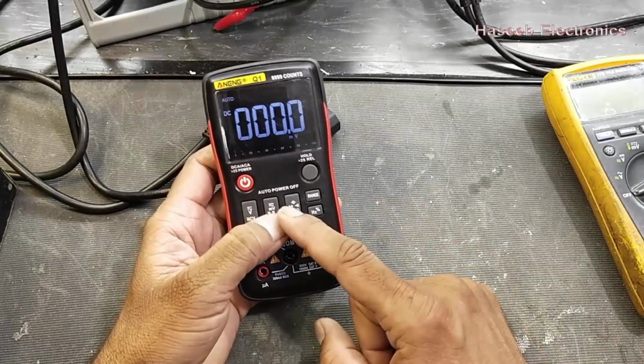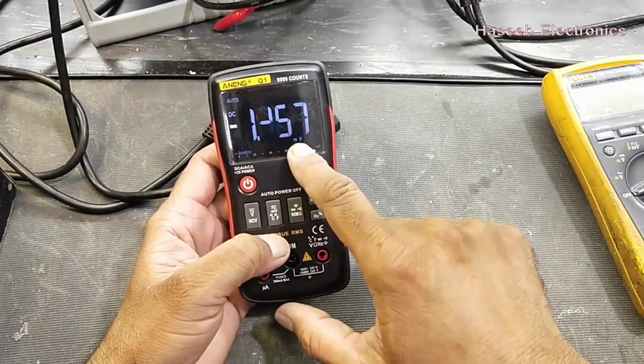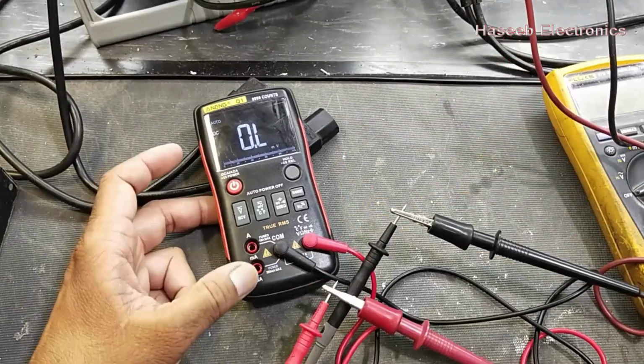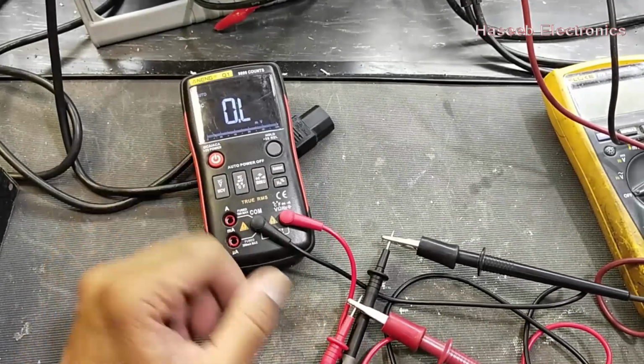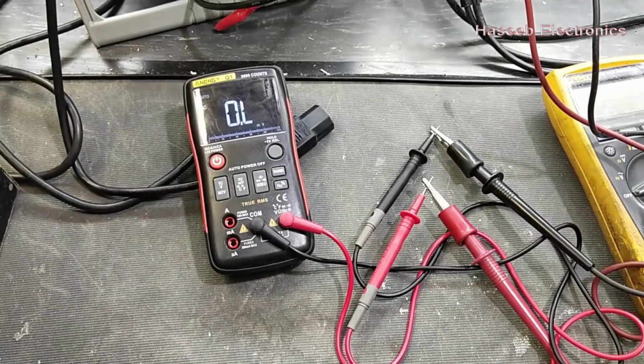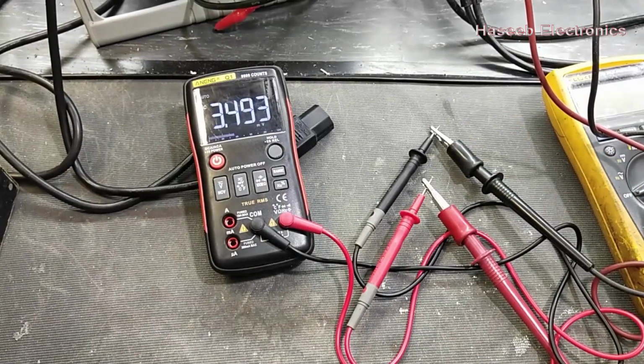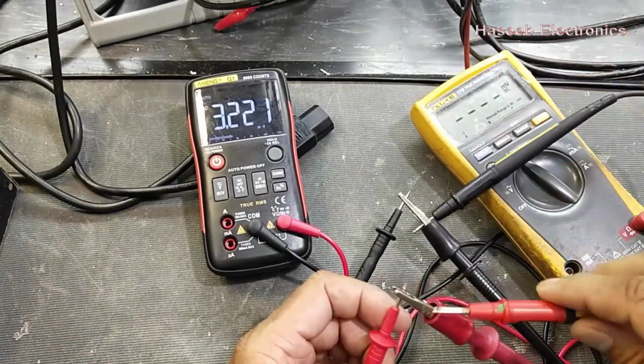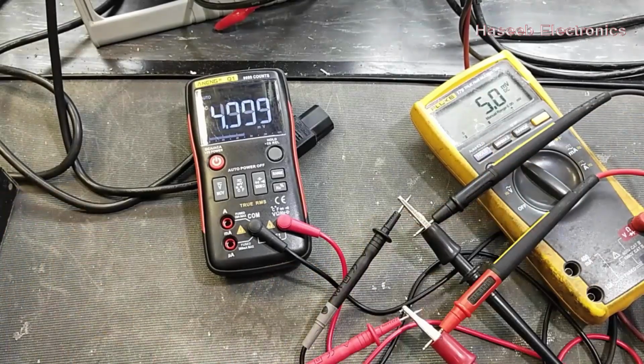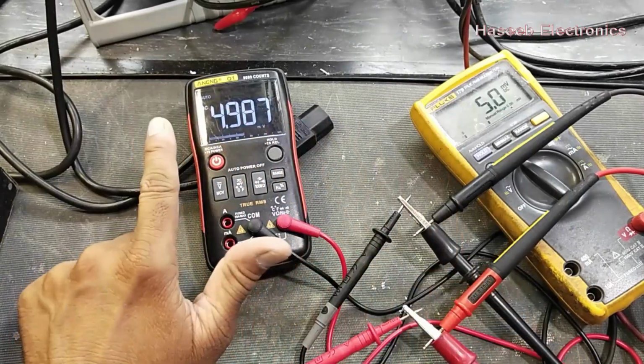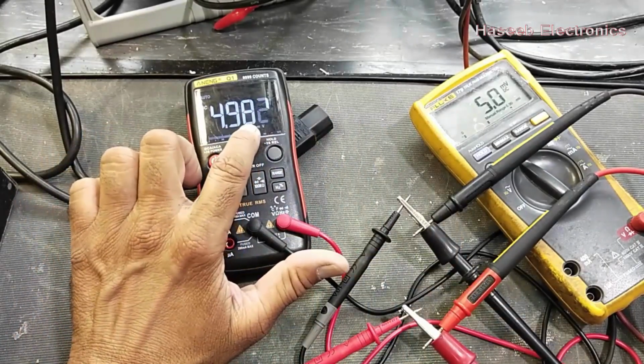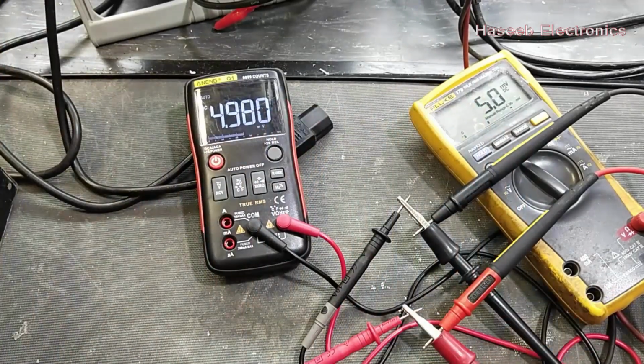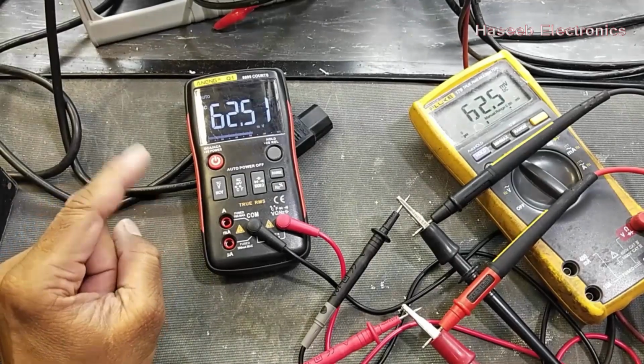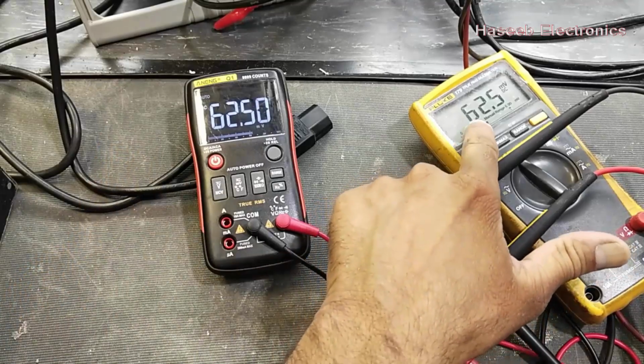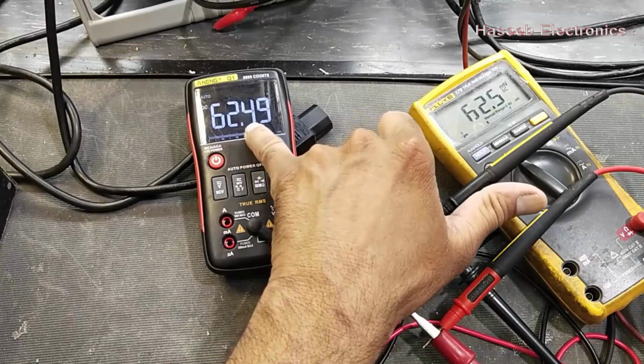To test millivolt in DC, power on, press this button, and now we are in millivolt range in DC. If I apply more voltage, it says over range, OL, overload, meaning the input applied is more than the multimeter range. When I decrease, I applied 5 millivolts, 5.0, 4.99. That's very nice. So it is reading with microvolt accuracy. So both multimeters are giving good readings. Here I applied 62.5 millivolts. It is reading 62.5, and this multimeter is reading 62.5 millivolt.